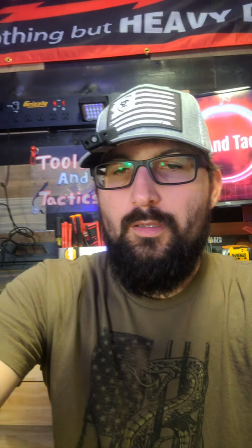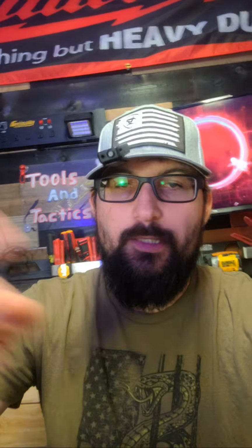So you can measure your inrush and say, well, 30 amps for a millisecond is okay on a 20 amp breaker. I think when we saw 25 amps on that, it was a 2-pole 20. So it's perfectly normal to see that much amperage. You just can't sustain it. If you're pulling too many amps, then you should.